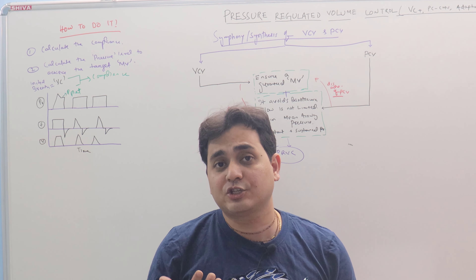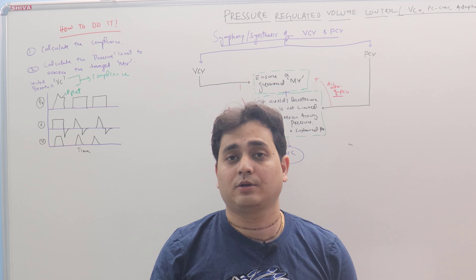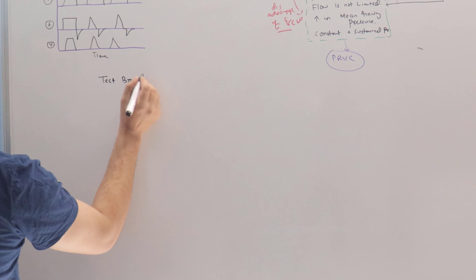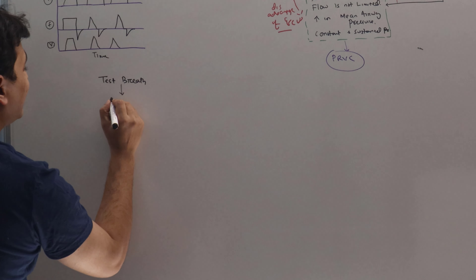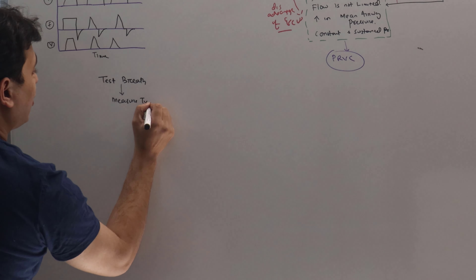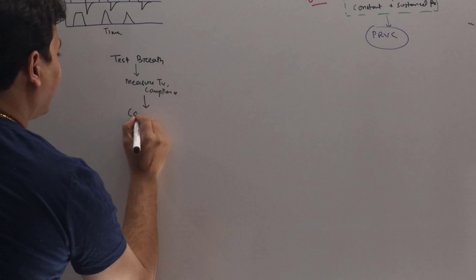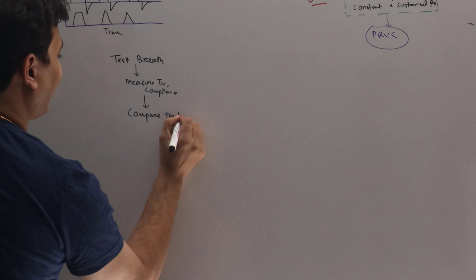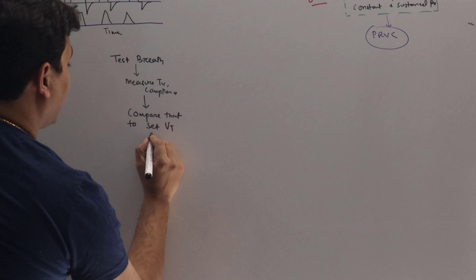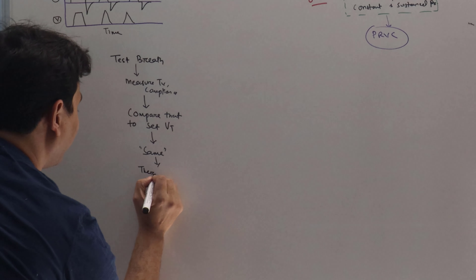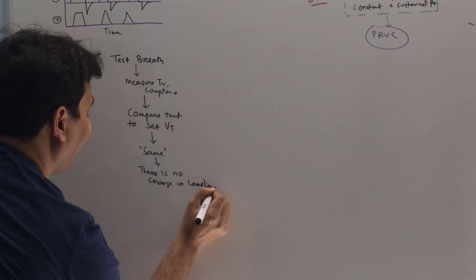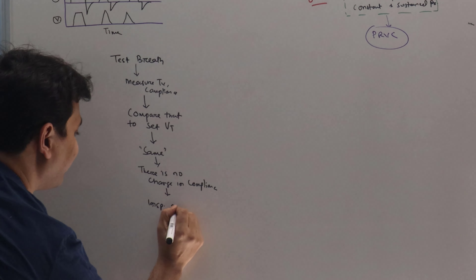Now we will discuss a very simple algorithm of how the ventilator decides the change in pressure depending on the change in compliance. You provide a test breath — as in here, the first initial breath is a test breath — and from there you measure the tidal volume and compliance. Now you compare that measured tidal volume to the set tidal volume. If it is the same, that means there is no change in compliance, so the inspiratory pressure remains the same.